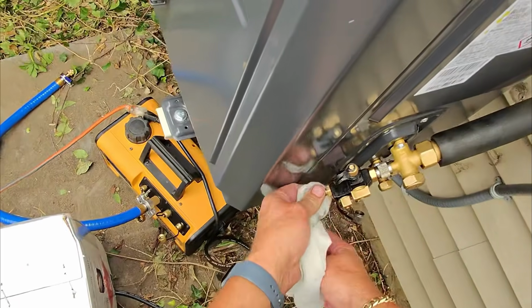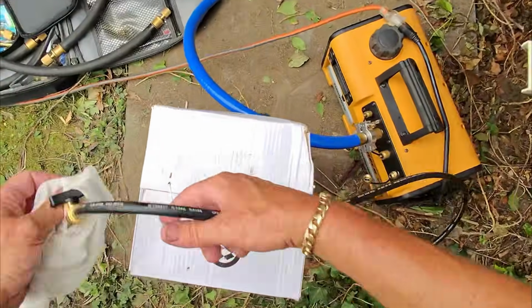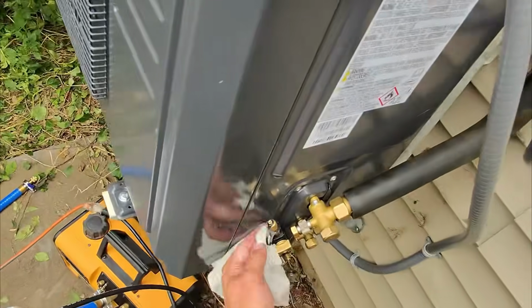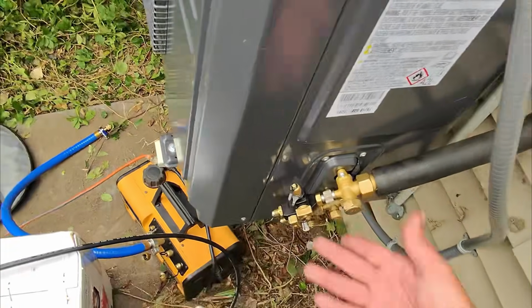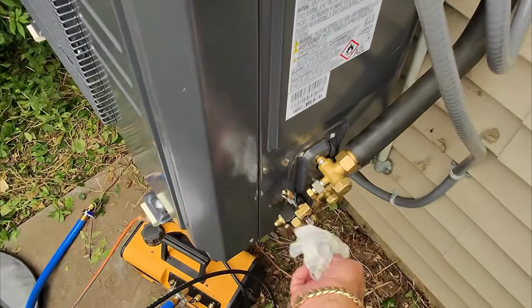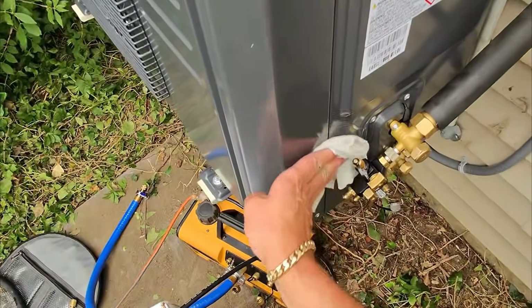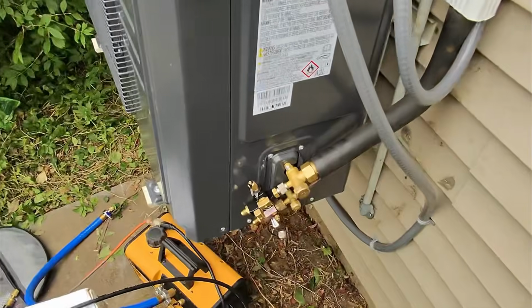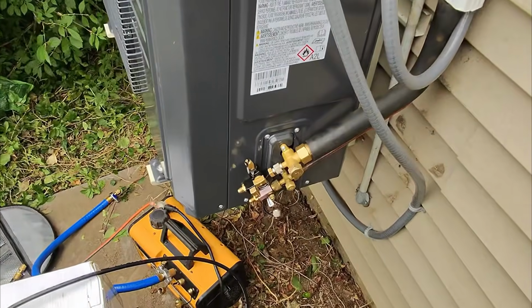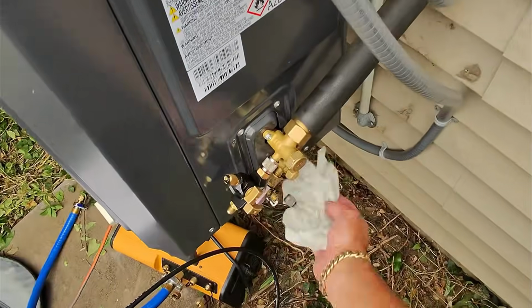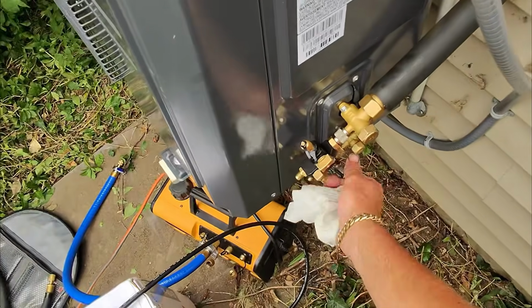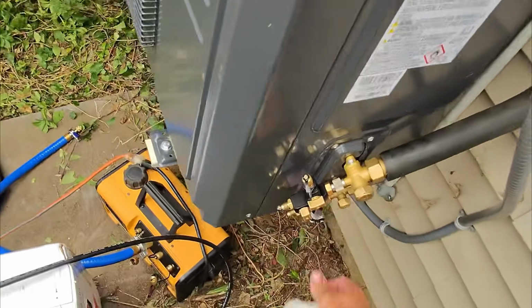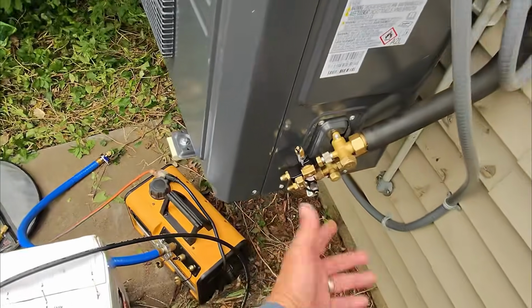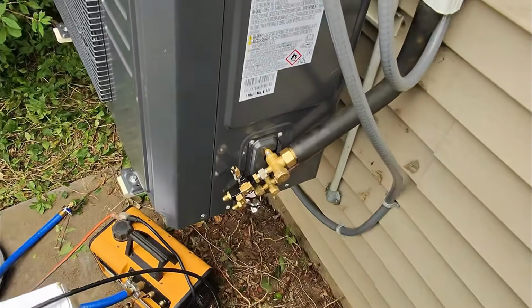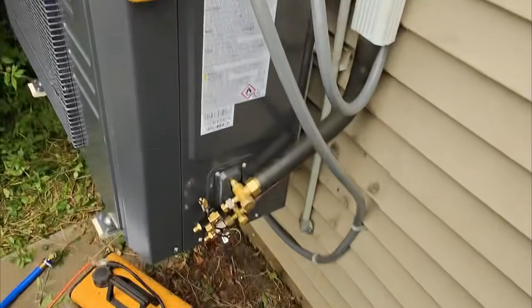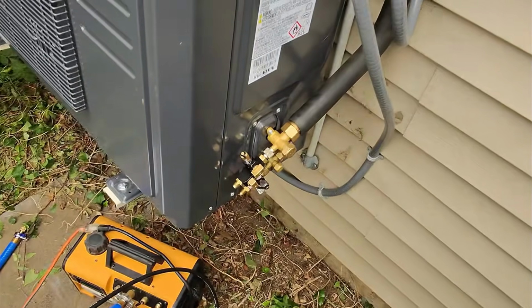Sorry guys for the cursing, but yesterday during a commissioning and startup of a 2-zone ductless system, the Fieldpiece Schrader core removal tool was acting up. Wasn't jiving, was leaking. So I started using my old Appion to the rescue. Problem solved. And now today, this loosens up, and when you loosen this up, it leaks out refrigerant. How is that even possible when this is closed? Come on, you saw that, right? How is that even possible?